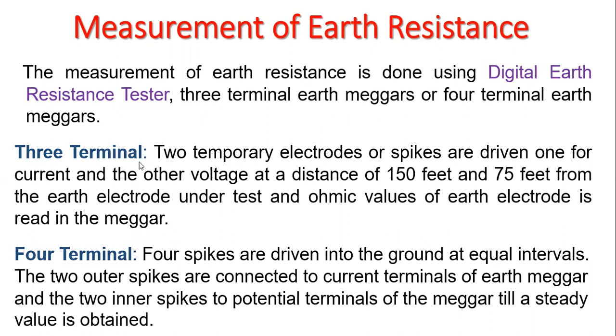First of all, the 3-terminal earth megger. In that, two temporary electrodes or spikes are driven in, one for current and the other for voltage, placed at a distance of 150 feet and 75 feet from the earth electrode which is under test. The ohmic value of the earth electrode is read on the megger. That means two electrodes are placed 75 feet and 150 feet from the earth electrode under test, and the reading is displayed and can be measured with the help of the megger.